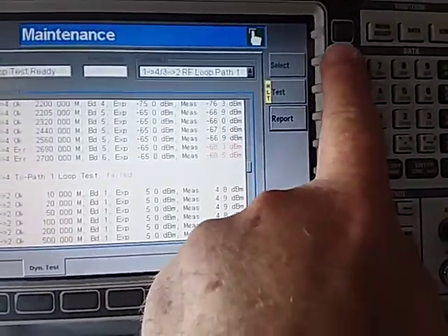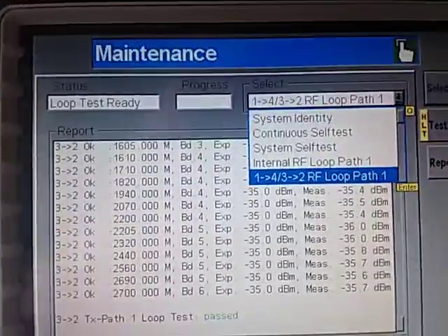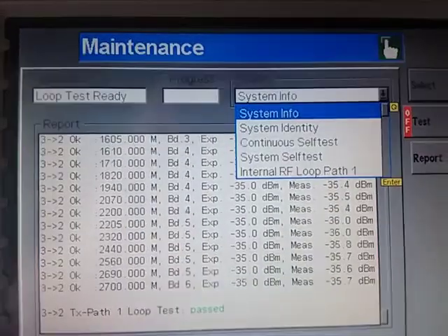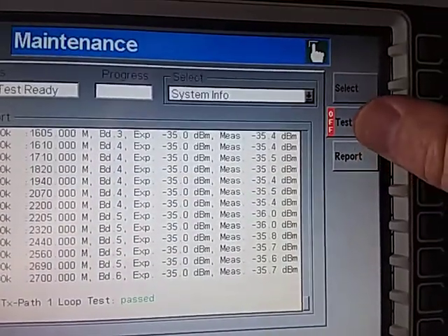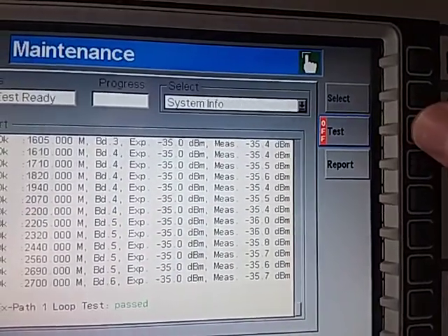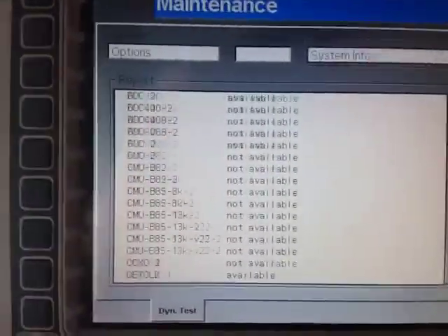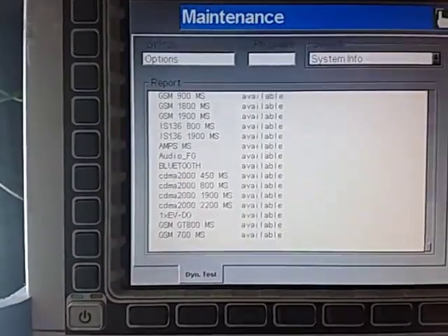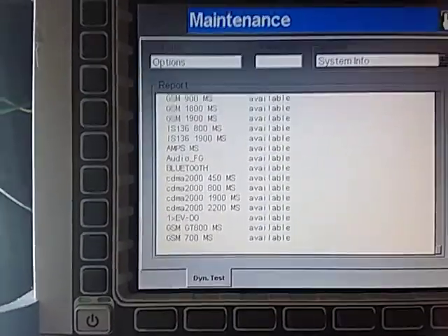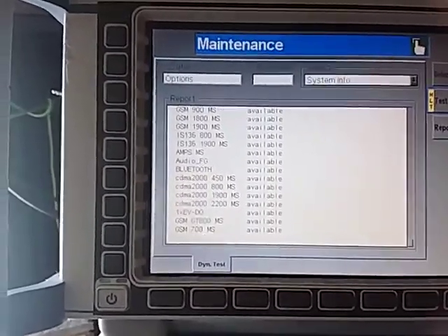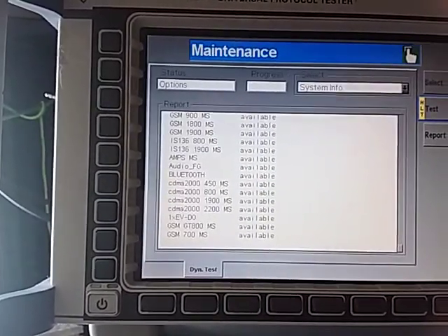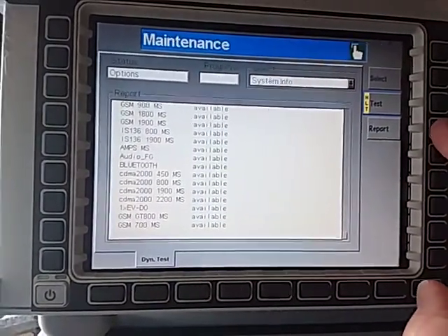There's some other tests that we can do. We just hit select and there's quite a range of tests here. System info will just report information about the system. If we press this button here and go okay, we can see the information. What this runs through is it sees what software is installed and what hardware is installed. It looks at the complete list of all the CMU accessories and it works through and identifies what is installed and what is not installed.